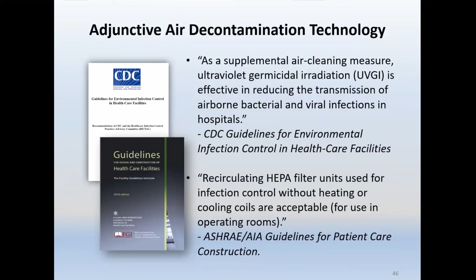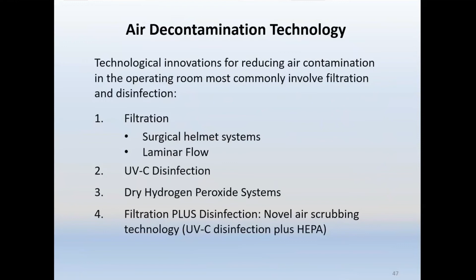Now, there are other air decontamination technologies that you might see in an operating room. It might involve filtration, like a surgical helmet system, or as we talked about, laminar flow. UVC disinfection, as I mentioned, there are some that can actually be built into the walls, up into the ceilings. There are some that are movable robots, as I mentioned. It's also a system that uses dry hydrogen peroxide and puts out a constant activity to clean any kind of bacteria, viruses that are in the air. And then there's this filtration plus disinfection, this novel air scrubbing technology, UVC plus the HEPA filtration.